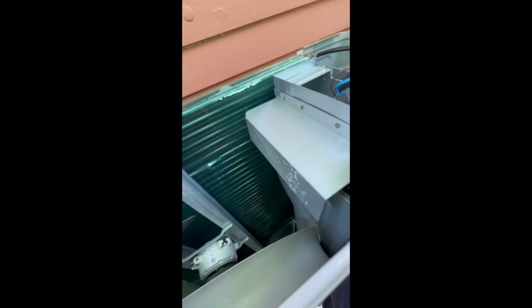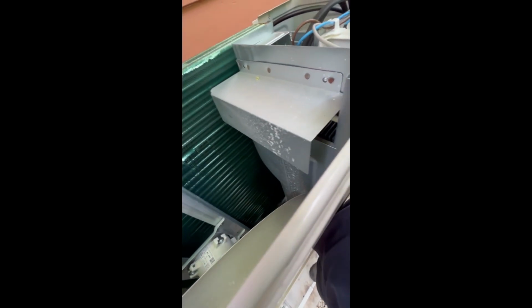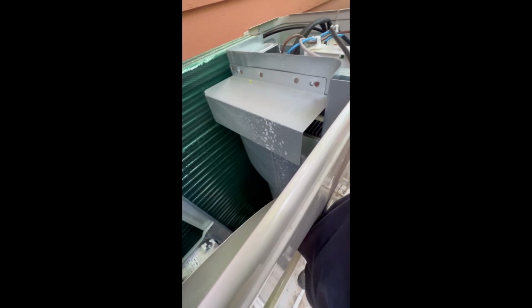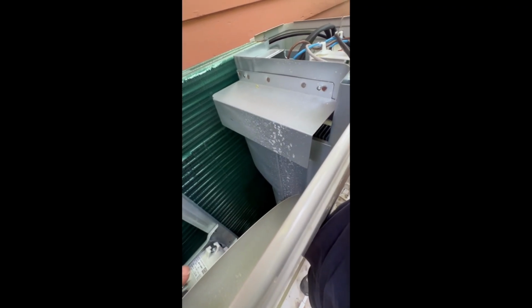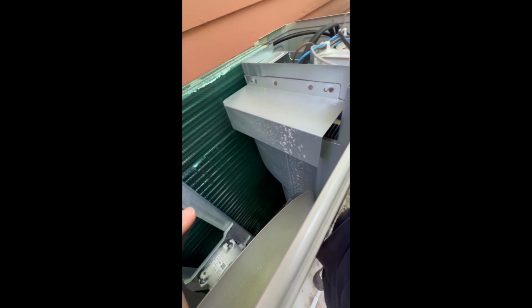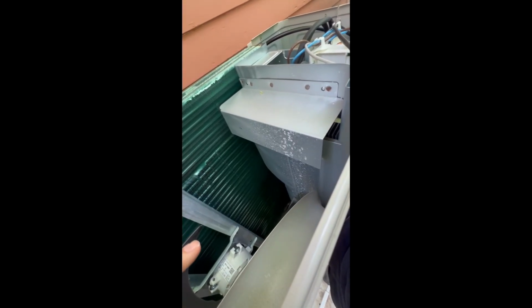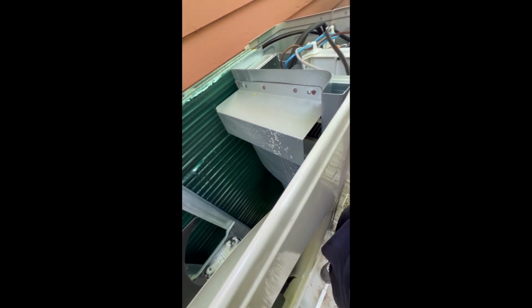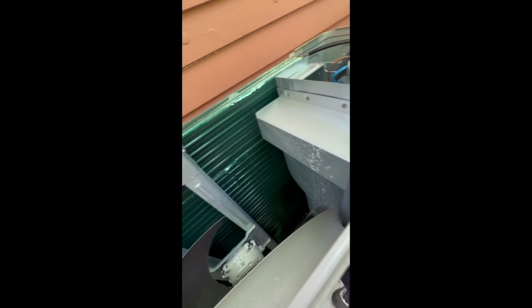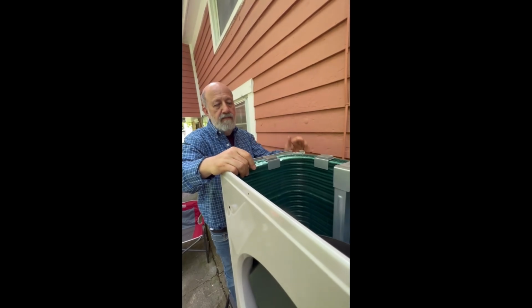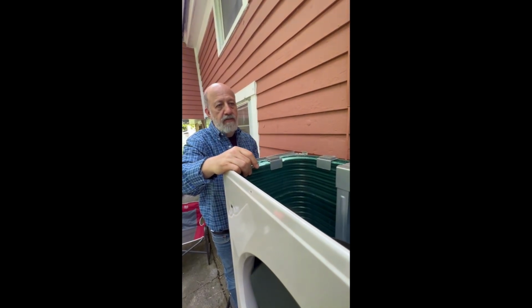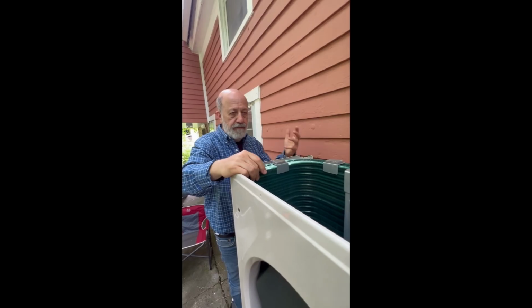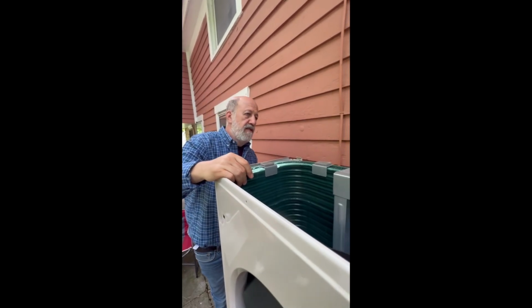Probably the biggest bypass from the control compartment into the fan section is this heat sink, and it is a vent to cool the electronics. There's a heat sink back there cooling the electronics, and they're letting outdoor air into this control compartment and then into the fan section without going through the heat exchanger. If we reduced that air bypass, more air would go through the heat exchanger. We would be raising the efficiency of the whole system.